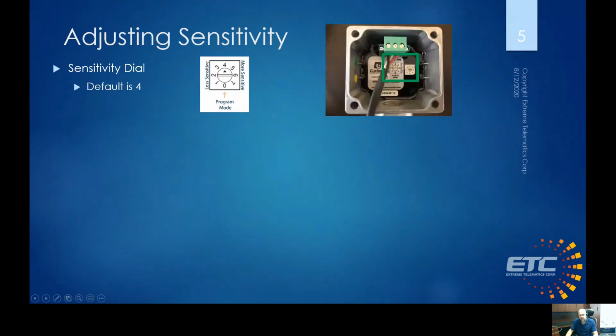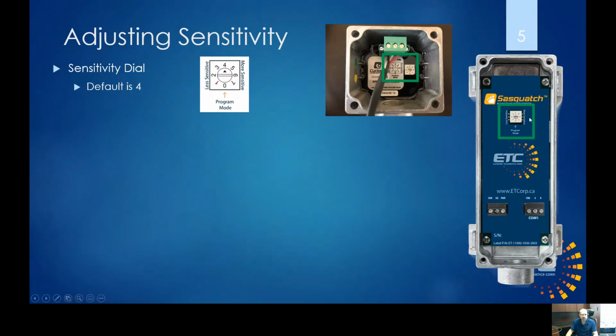So you can see here, this is where it's located on the Cyclops, and that's on the Sasquatch. Sasquatch doesn't have anything to do with the velocity, but just when we start calculating velocity in a plunger arrival. So 1 is the minimum sensitivity, or it's the biggest threshold that's required to trigger it, and 7 is the max sensitivity, or the smallest threshold. And we'll show you a demo later on what that looks like.